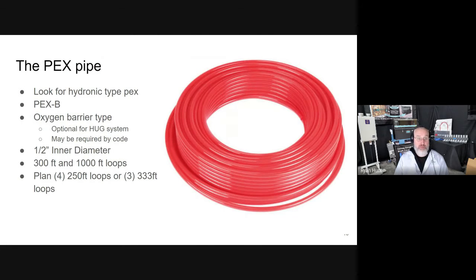Now, what type of PEX? We usually work with PEX B, 1/2-inch diameter. That's what we recommend. There's other types of PEX. Oxygen barrier type is important for code. For a lot of traditional hardware, it's important, and so that's why they made it for the code. They don't want oxygen in some of the boilers and other metal parts that may be susceptible to it. Our system doesn't have that sensitivity, but we usually recommend people put it in just so that there's no disagreements anywhere. We use 1/2-inch diameter.